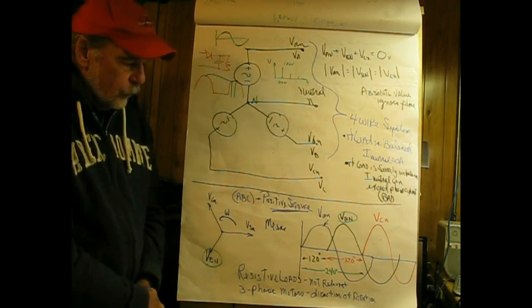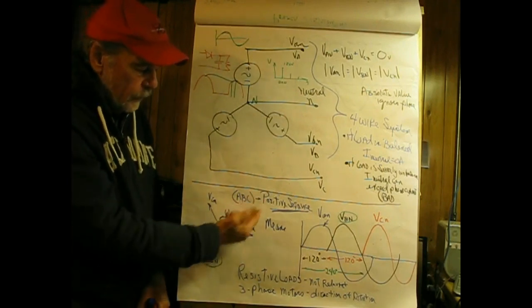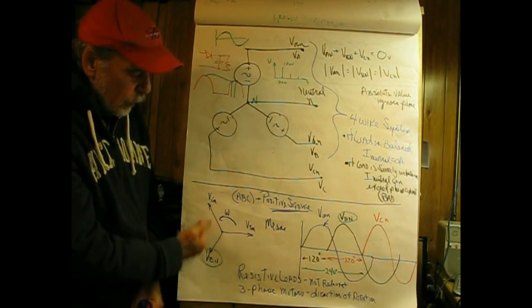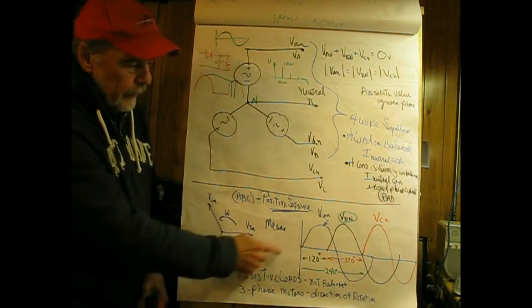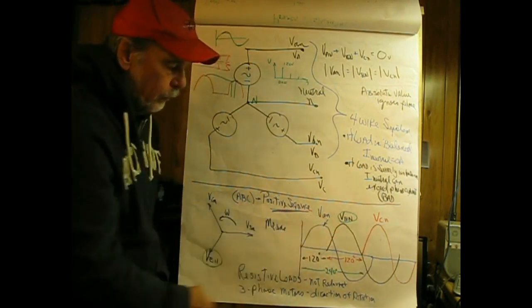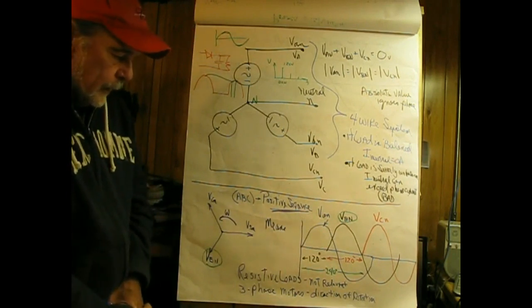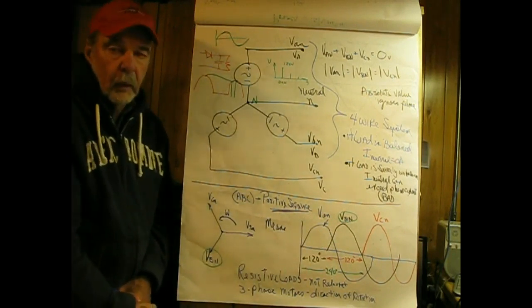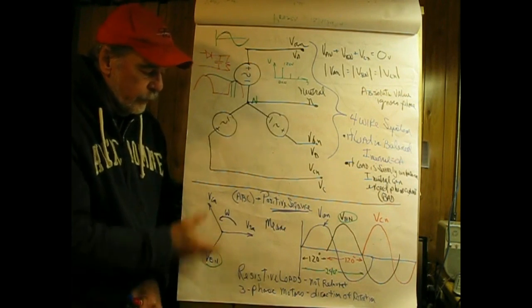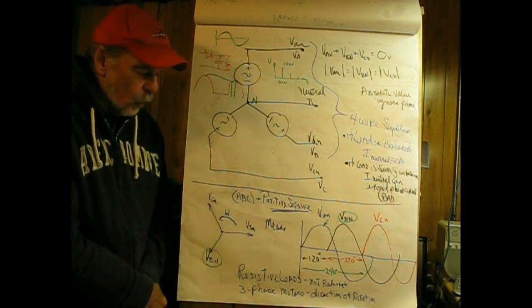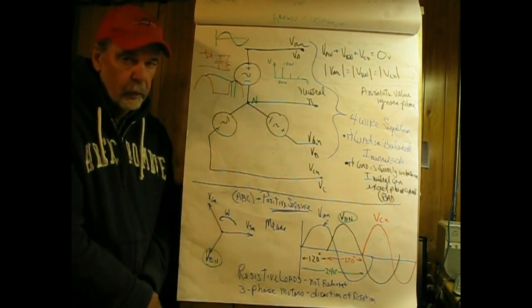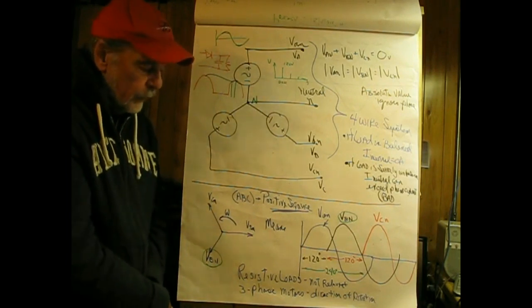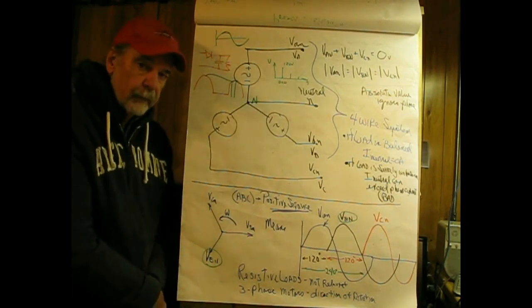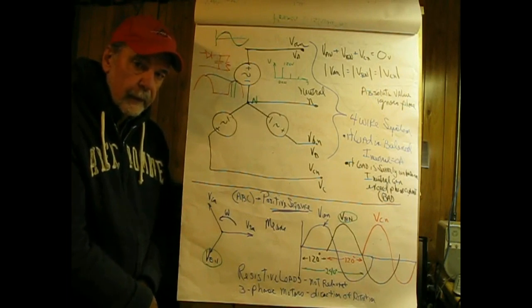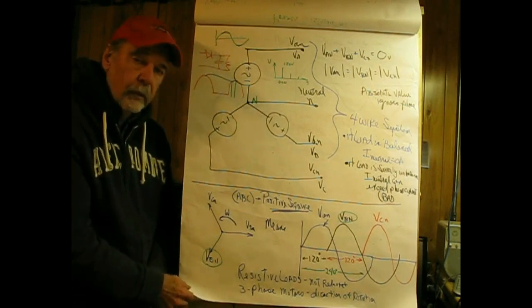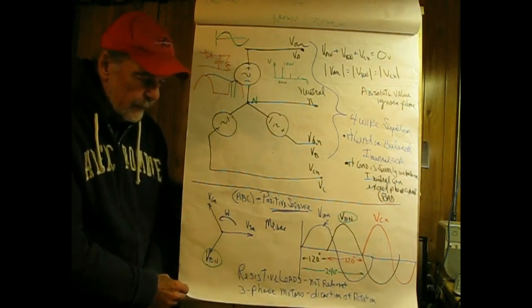We have two sequences here. ABC is called a positive sequence, and here I've sketched the order of that. In resistive loads, this doesn't mean a whole lot—the transformer outside of our homes is connected to one of these loads, and we really don't care. But if we're connecting machinery to this, it's very important that we get it right. A three-phase motor running backward in certain equipment can do a lot of damage.